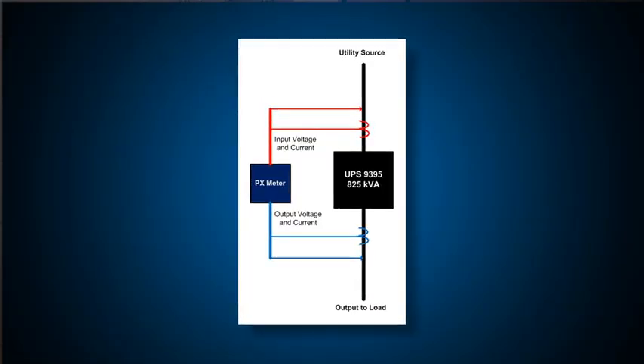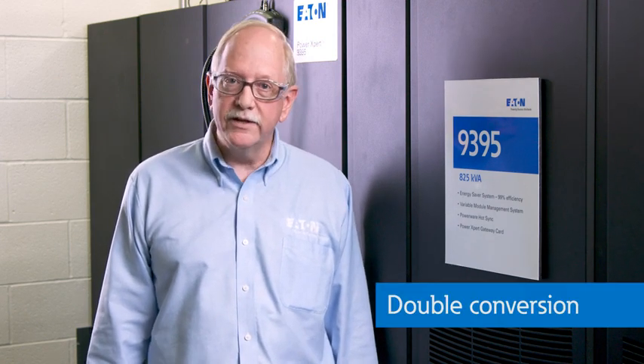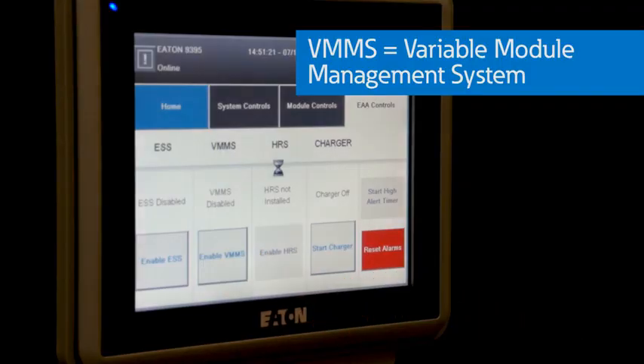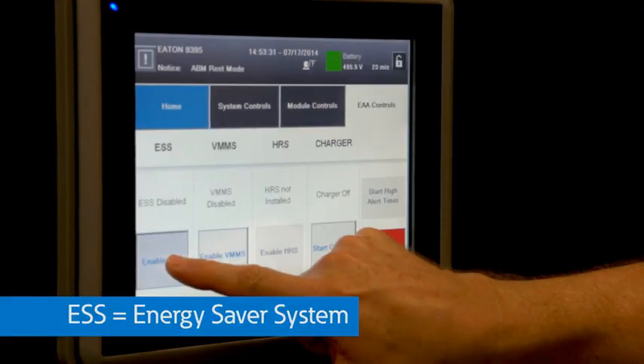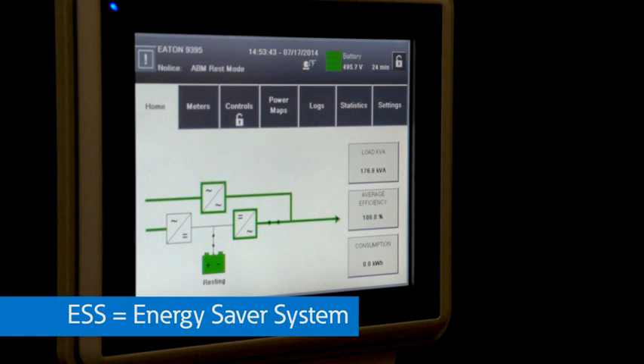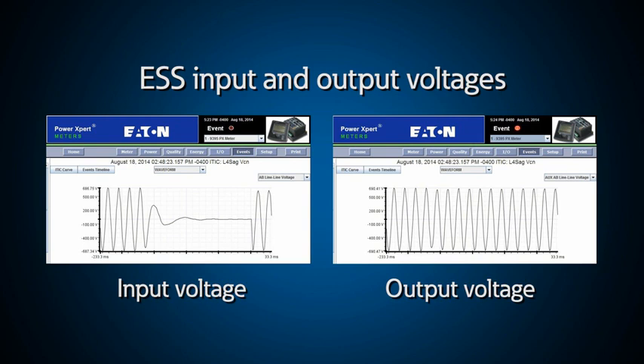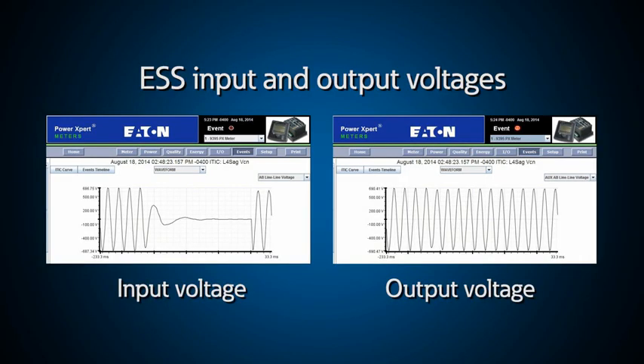Here's how we use them on our UPSs. Here at the Raleigh Experience Center, we can show you how our 9395 UPSs work in double conversion, variable module management (VMMS), and high efficiency mode (ESS). With the auxiliary channels on the power expert meter, I can show you the input and output voltage before and after a voltage anomaly to demonstrate the fast transfer time during our ESS mode of operation. As you can see here, the transition time for ESS is less than two milliseconds.